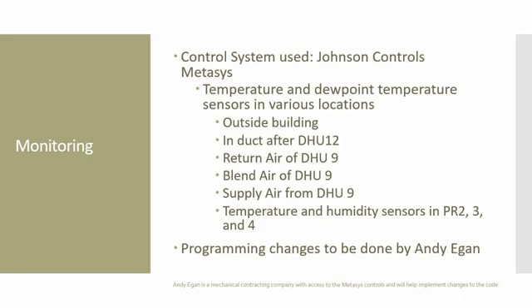Monitoring of all air handling systems in the Meadowbrook facility is done using Johnson Controls Metasys software. There are temperature and dew point sensors located in various areas of the building, including outside, in ductwork from DHU12, in the return air and blend air duct of DHU9, and the supply air leading from DHU9 into the dry clean rooms. There are also temperature and humidity sensors located inside the dry clean rooms in pilot rooms 2, 3, and 4. Programming changes will be done by the company Andy Egan.